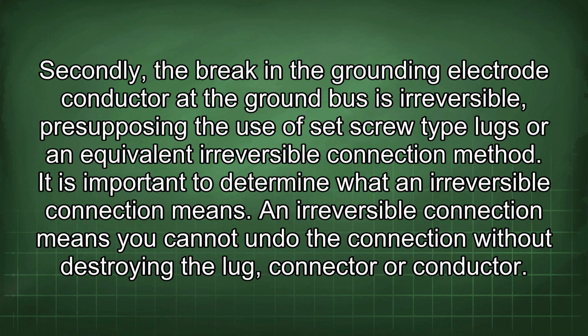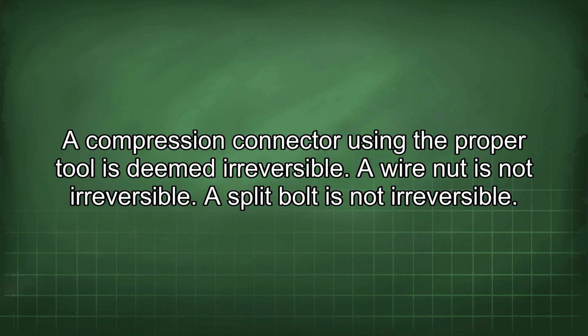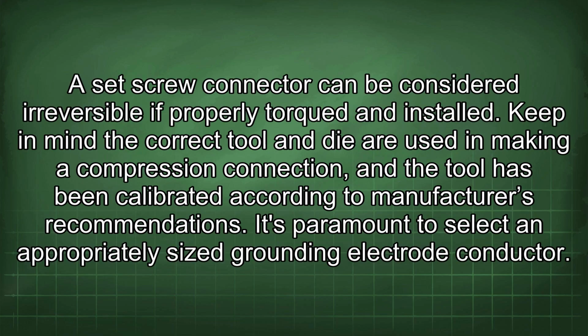It is important to determine what an irreversible connection means. An irreversible connection means you cannot undo the connection without destroying the lug, connector or conductor. A compression connector using the proper tool is deemed irreversible. A wire nut is not irreversible. A split bolt is not irreversible. A set screw connector can be considered irreversible if properly torqued and installed.